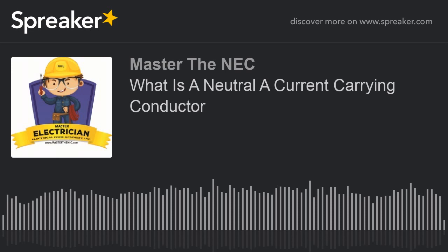And again, in our case, if it's a black, red, blue in there, and we have a four-wire Y system with nonlinear loads, a major portion of that takes place. If that's the case, then that fourth conductor, current carrying conductor, will be the neutral. And that has to be taken into consideration. And there's a good chance that depending on the amount of nonlinear loads that you're dealing with, it could carry 2 times the ampacity that any of the phase conductors are carrying. Okay, so always keep that in mind in that design.